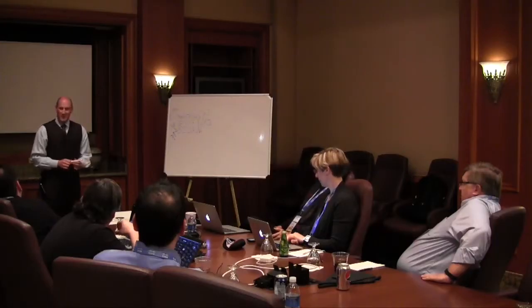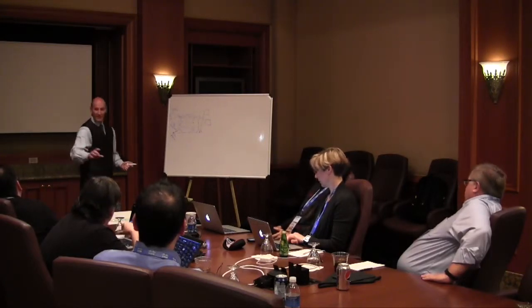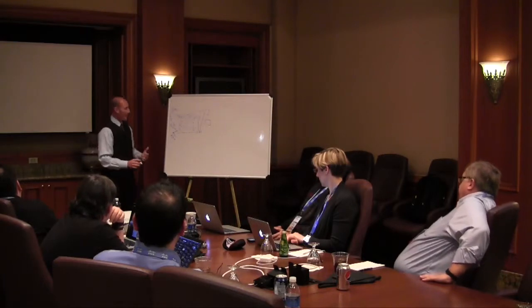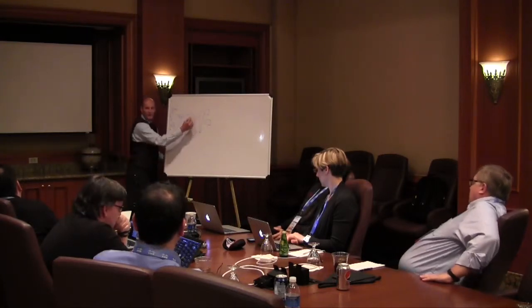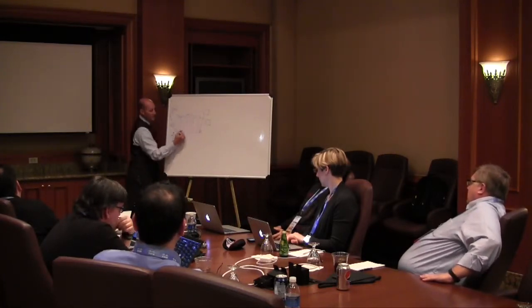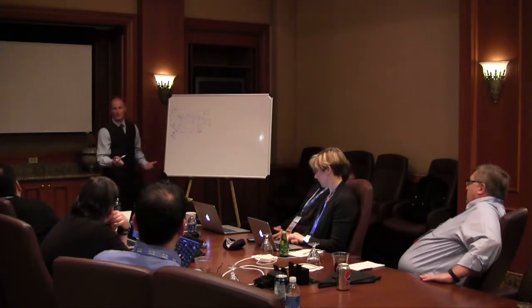Why did you do 4x4 as opposed to leaf spine? As opposed to just pure leaf spine? Pure leaf spine. Because if I did pure leaf spine, I'm back to that concept of constantly going up when 80% of my traffic is inside this node.